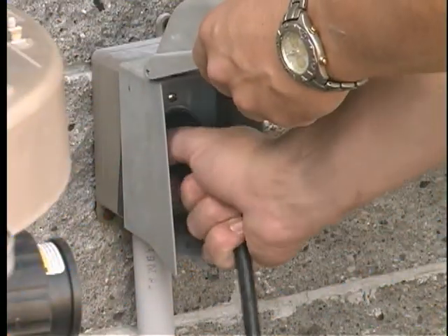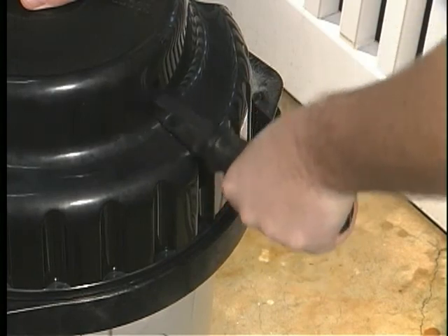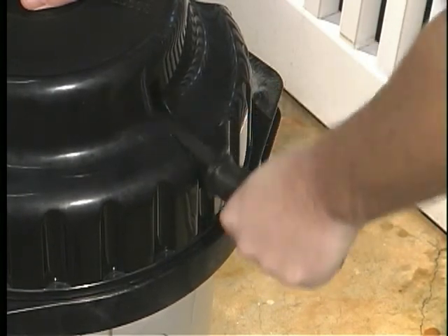Turn off the electricity to the pump. Loosen the air vent at the top of the tank to release the pressure. Ease down on the pump handle and raise rapidly ten times or more to loosen the DE inside the tank, with the air valve still open.